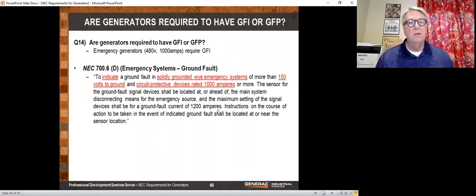All right, let's go on to question 14. Are generators required to have ground fault indication or ground fault protection? They have to have ground fault indication only if they are 480 volts, 1,000 amps and more, and on an emergency system. So if you're in a non-emergency system, you don't necessarily need it. If it's under 1,000 amps, you don't need it. And if it's 120/240 or 120/208, you don't need it.